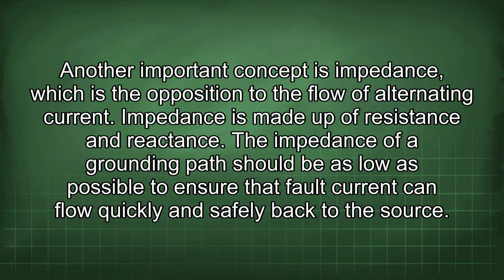Another important concept is impedance, which is the opposition to the flow of alternating current. Impedance is made up of resistance and reactance. The impedance of a grounding path should be as low as possible to ensure the fault current can flow quickly and safely back to the source.